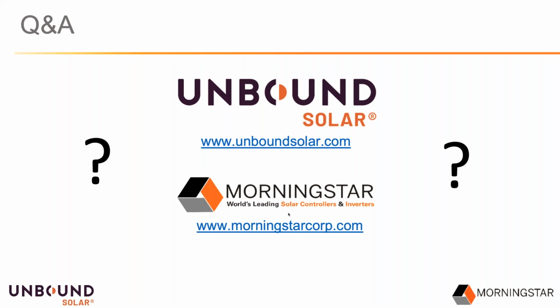I'm not sure what CKT stands for. I'm not either. It's an abbreviation, small letters, CKT period. Okay, yeah, and I think basically what you're trying to do in the design is design a system that's never going to go over voltage at the extreme low temperature. Sometimes it's a little bit difficult to know how cold it's going to get in an area. Sometimes that data can be hard to get if you just don't have climate data. You're not looking at the average low, you're looking at the extreme low. How cold is it going to get as a worst case? And then essentially you'd want to design a system that's never going to go over voltage at that extreme low.